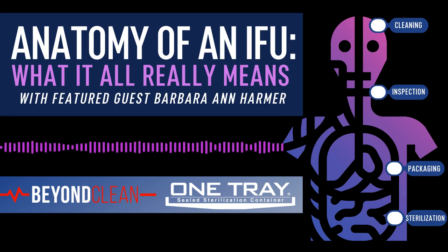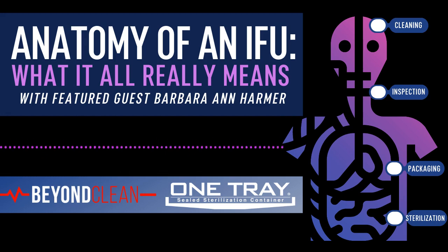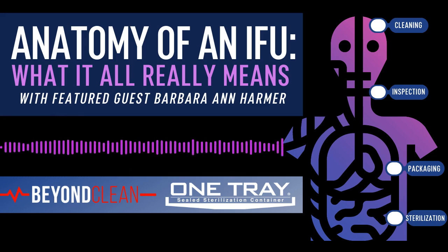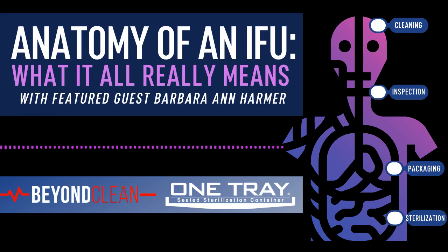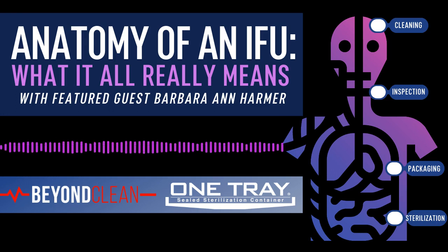This IFU is one that very few people have read in its entirety. The sterilizer IFU, amongst other things, will tell you how many trays you can run in one load when using rigid containers, and the weight of the containers. Most will be 25 pounds, but there is a sterilizer out there, ironically, that has a maximum weight of 17 pounds per tray. And I've spoken to some individuals that actually purchased this sterilizer and were not aware that this was how the sterilizer had gone through the FDA process.